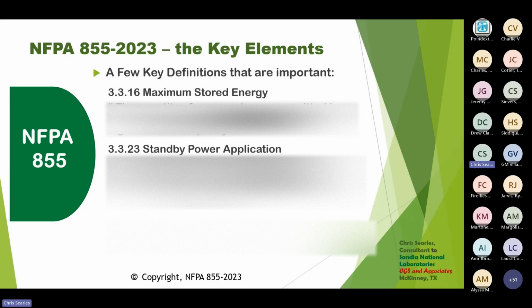So the difference between a standby power application and a new energy storage application really only means that in a standby application, we're keeping the battery on charge continuously, and it's supposed to be able to supply its full capacity rating for the time that you specified the battery had to support the loads you're keeping, or critical loads that you can't afford to have go down. In an energy storage application, there's a lot of cycling involved, which may involve partial states of charge, and they're differentiated in standby, but with some technologies, the technologies are the same and it muddies the water.